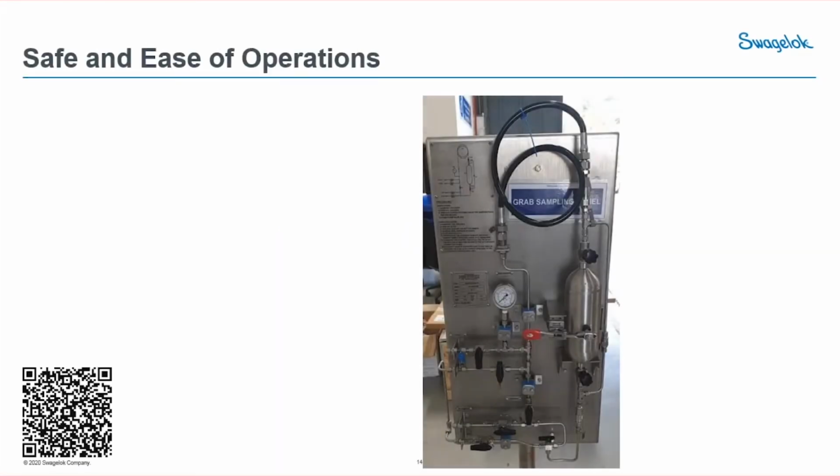This is an example of a grab sample system where traditionally this has always been the design that we put on site. So this sample system that you see over here is still sampling from bottom up. Good idea. That is a good sampling design, but herein lies one of the problems. This design was probably from 2015, so about 5 years ago, and we still see plenty of it today, even new ones. Now, the problem we face here is that if you were the operator, it could be very daunting to take a sample.